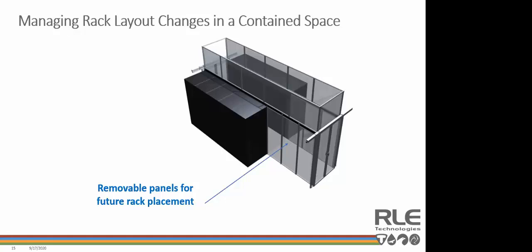When we talk to customers, one of the concerns that a lot of them have prior to installing containment is that if they install containment now, they won't be able to manage rack layout changes or expansion with growth. But really, in most cases, containment can be implemented with growth or plan changes taken into account. And here's an example of a system that was designed so that panels can be removed and replaced with racks as this row build-out continues. And really, this can be done for just about any configuration.